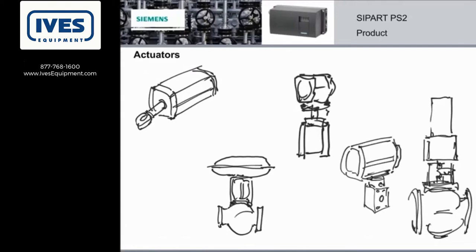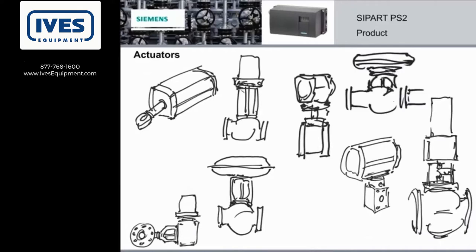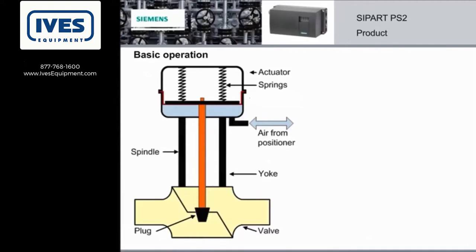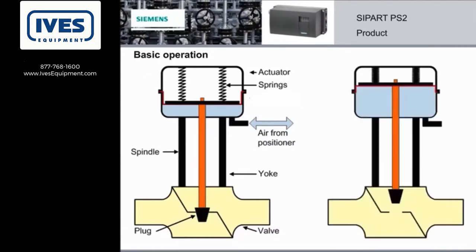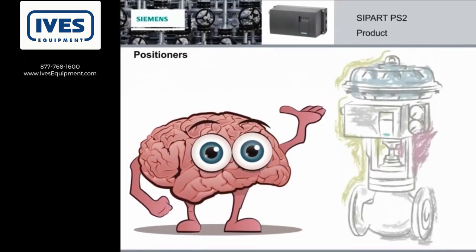An actuator is a type of motor, and can be electric, hydraulic, or pneumatic, and single acting or double acting. Whatever the type, it is the actuator that moves the position of the valves, and this movement can be linear or rotary. The basic operation is very simple. On the left is a linear, single acting actuator with the plug in the closed position. To the right is an open valve allowing the material to flow through. So how does the actuator know when and how much to move the valve? It's the positioner.